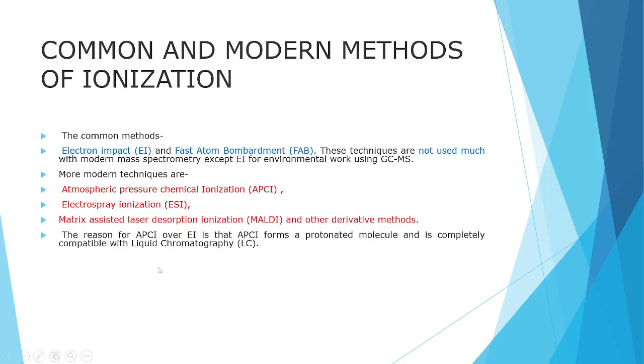The reason for APCI over EI is that APCI forms a protonated molecule and is completely compatible with liquid chromatography. This is a comparative account. EI is more likely to fragment the ion leading to possible more ambiguous identification of the molecule weight and is incompatible with LC. So this compatibility with LC, EI does not have when we compare with APCI.